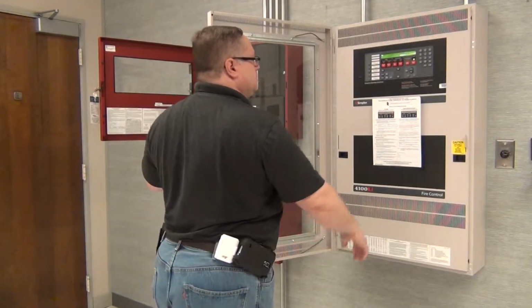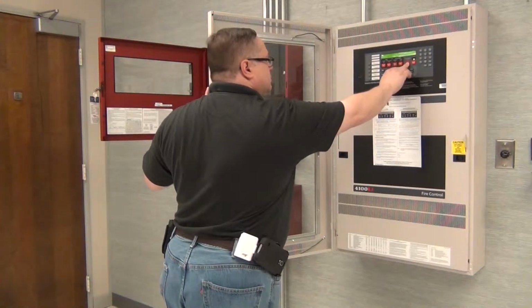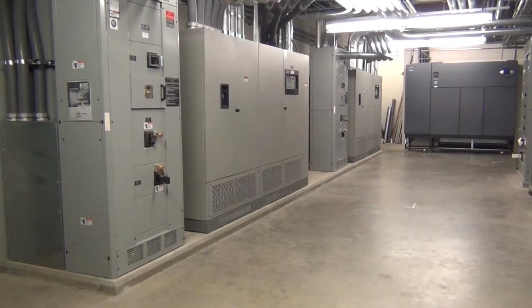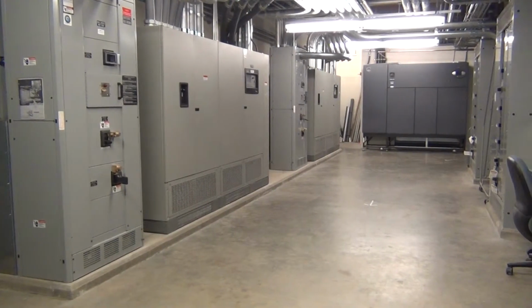For cooling, we use three 250-ton Trane water chillers and eight 50-ton air handlers off of that. We have 500 tons of chilled water available at any time, as well as 250 tons in reserve.